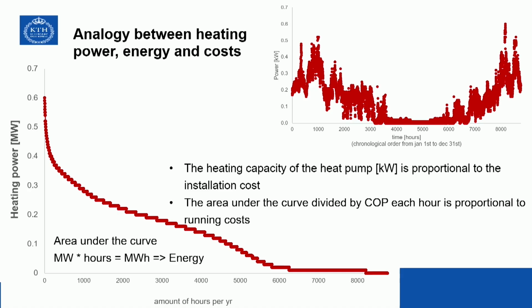Another aspect is that the y-axis of this chart is the installation cost. Normally, the installed power you decide on times the price per installed ton of refrigeration, or installed megawatt in this case, gives the installation cost. If you multiply by the number of hours, you get the running cost. So this type of graph gives us a good technical base, but also information about the life cycle cost of the installation.